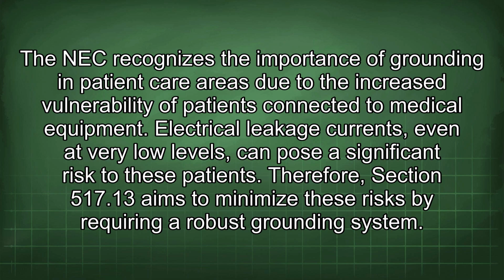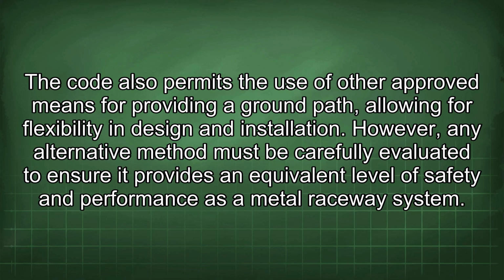Therefore, Section 517.13 aims to minimize these risks by requiring a robust grounding system. The code also permits the use of other approved means for providing a ground path, allowing for flexibility in design and installation. However, any alternative method must be carefully evaluated to ensure it provides an equivalent level of safety and performance as a metal raceway system.